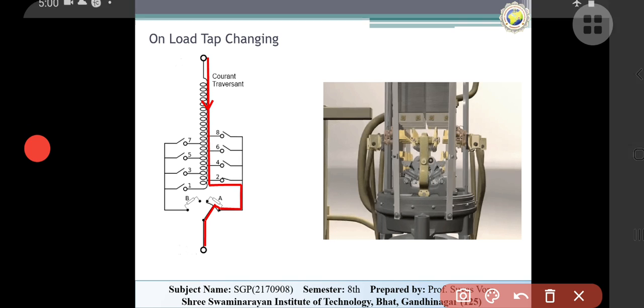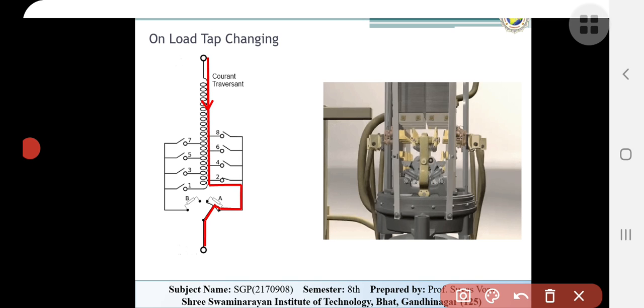So in on load tap changing systems, generally for the power transformer, tappings are provided on the windings. We know that here you can see the tappings are provided. Depending on the load, the tapping positions change, hence the turn ratio may also change. Now compensating for the effect by varying the tapping on the differential protection scheme is not practicable. It means that this switch, you can see this switch is moving from here to here.